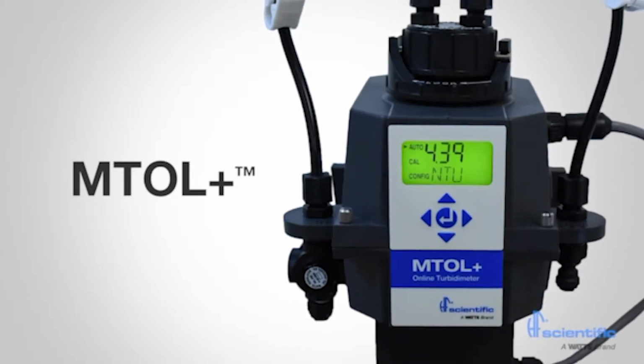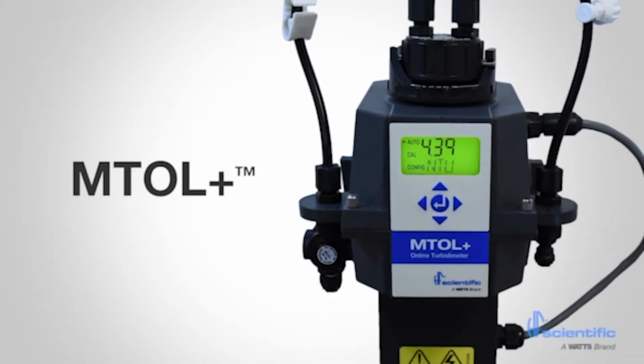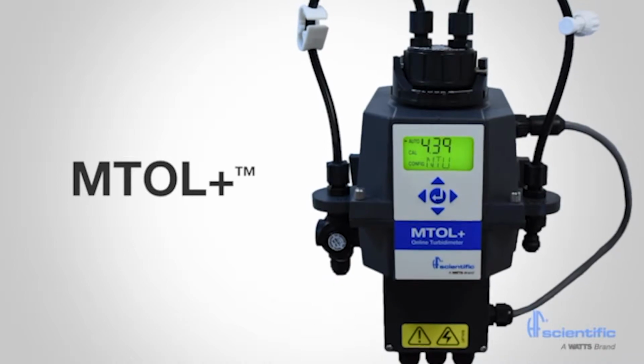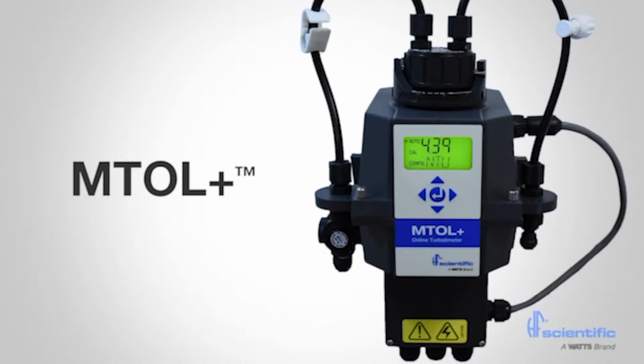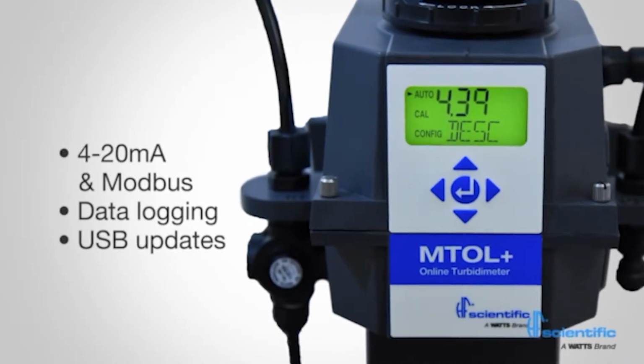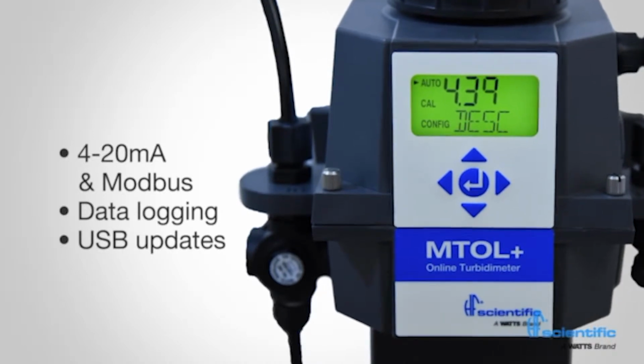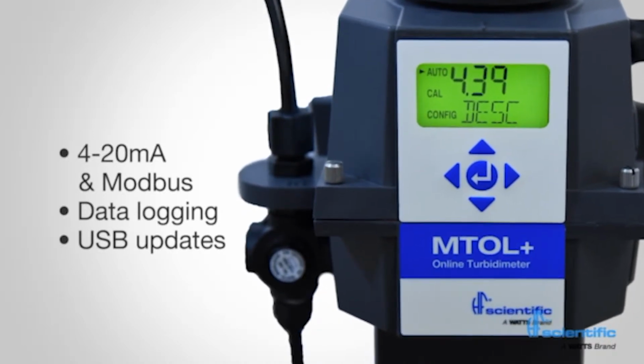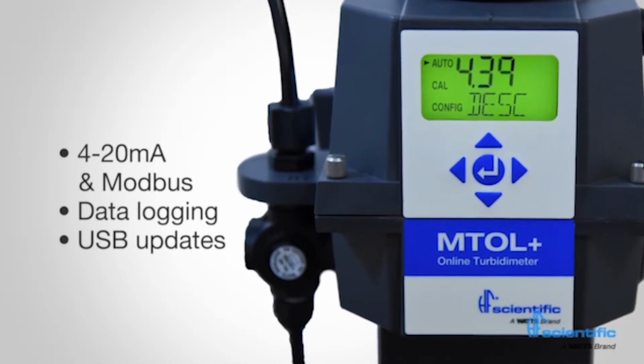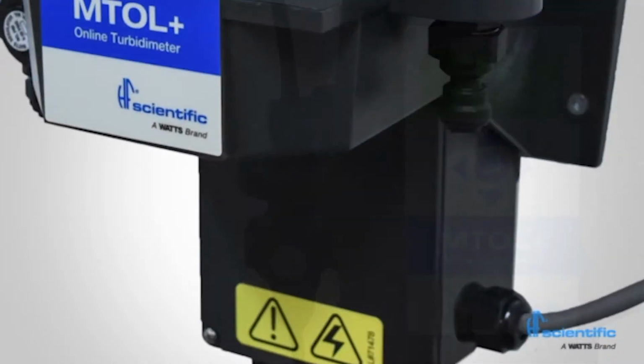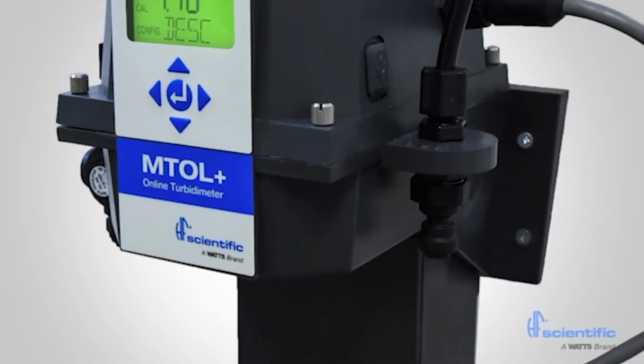While this instrument has a lot in common with the previous generation, it has been redesigned with a 32-bit ARM core processor to allow for enhanced features. Other new features include simultaneous 4 to 20 mA and Modbus outputs, data logging of readings, USB software updates, and USB data downloads. The MTOL+ is factory calibrated and programmed with default settings out of the box.